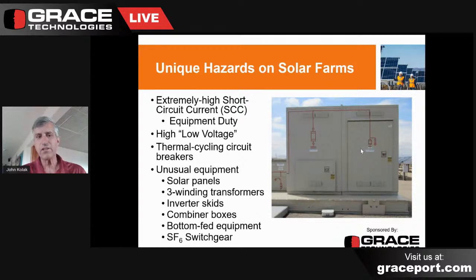We have done arc flash studies and found that even the 34,500 volt circuit breakers in a substation were actually over duty. There was more short circuit current there than they could interrupt if it was an actual fault of that magnitude. So equipment duty is a very important concept to consider. And even in substations, we've had experiences where you could have, as I said, overcurrent devices that were not able to interrupt the current flow. And that, of course, is something that we need to address from the engineering side when we're able.